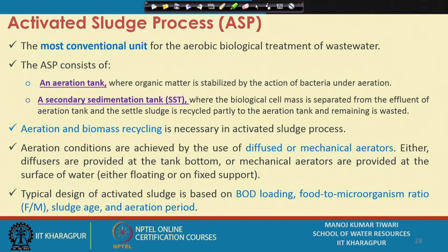So what is the activated sludge process, commonly known by the acronym ASP? It is the most conventional unit which works on aerobic principles of wastewater treatment. The organic matter present in the water, or the BOD, is degraded or reduced by aerobic degradation or aerobic decomposition in a reactor or unit which supplies oxygen, because it is an aerobic system.